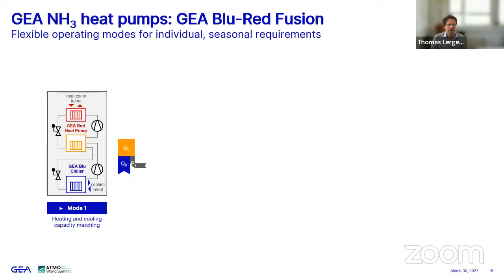heating energy of the hot side of the systems. So basically this orange block is the intermediate capacity, and then you're adding the driving power of the high stage compressor, and this provides you with your heating energy. In this mode, this is firmly linked. So depending on your temperature requirements, you can either say, I have a specific heating capacity requirement, and then you have to provide the resulting cooling capacity with your heat source, or vice versa. You say you have a specific amount of cooling energy available, and I have a specific temperature requirement, and then if you have that blue amount available fixed, then basically you need to take what you're automatically receiving on the hot side.